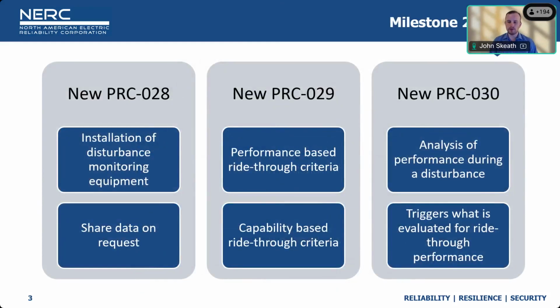Milestone 2 carried with it 3 new standards: PRC-028, 029, and 030. The other parts of milestone 2 were to install monitoring devices within the generation fleet, PRC-028, which I'll go over in a bit, and PRC-030, which requires generator owners to analyze root cause during a disturbance and evaluate the ride-through performance of specific generators when certain reductions are seen at the plant level. PRC-029 identified very specific performance-based ride-through criteria for voltage or frequency excursions, with some processes for exceptions. That standard sets the expectation for inverter-based resource interactions with the bulk power system, and separates the ride-through characteristics and protection-based performance for disturbance ride-through from its synchronous counterparts in PRC-024.